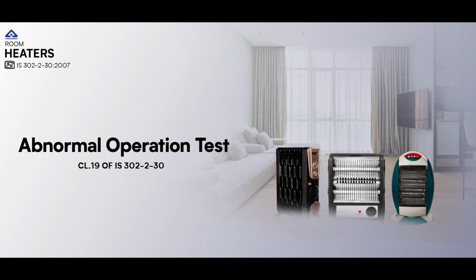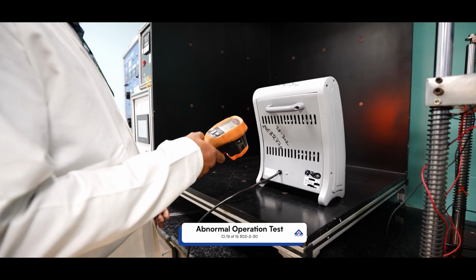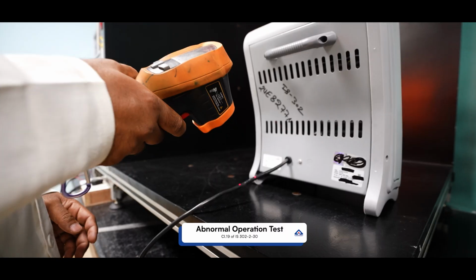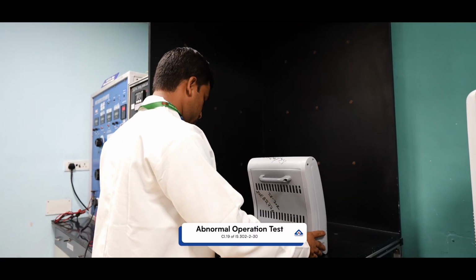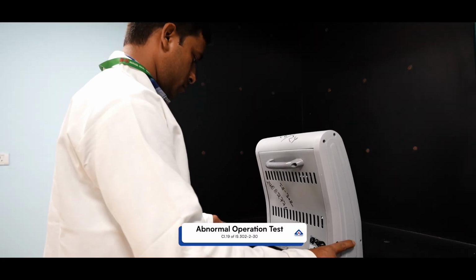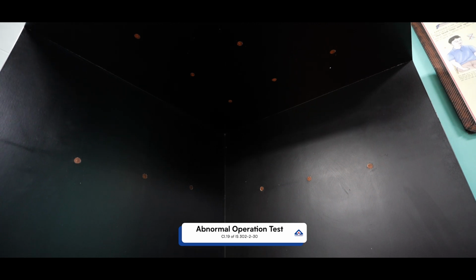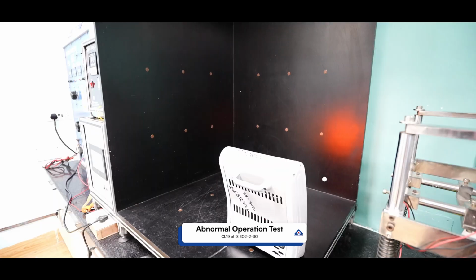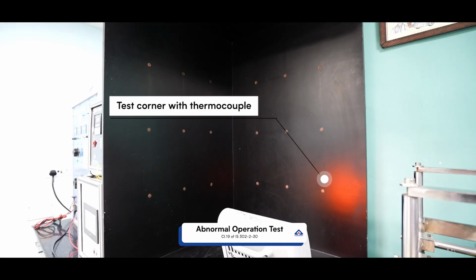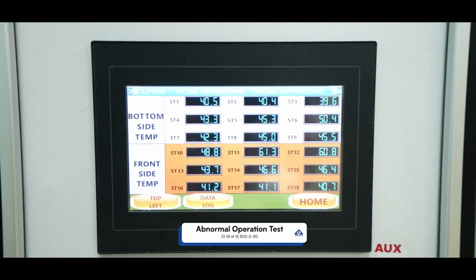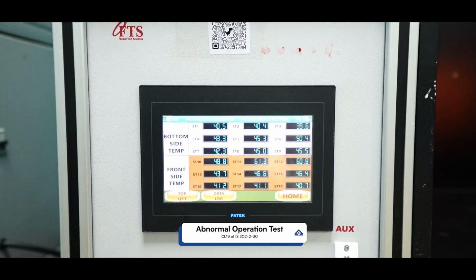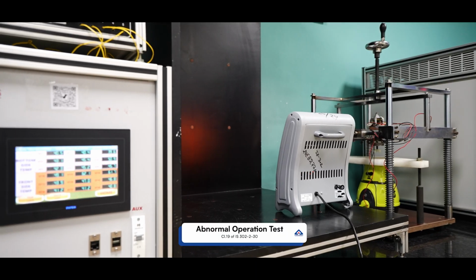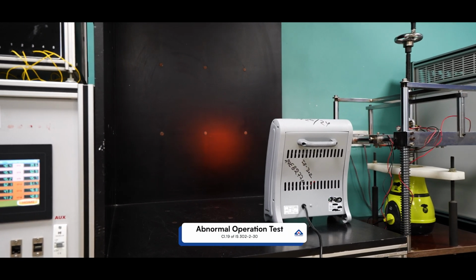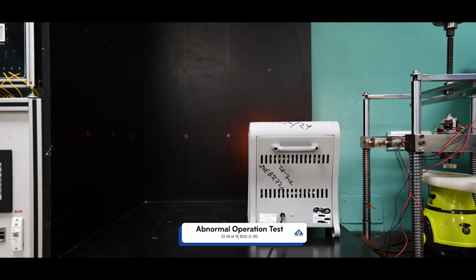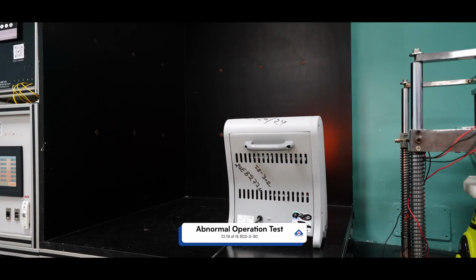Abnormal operation test. This test simulates abnormal or careless operation of the heater, such as when a motor rotor is locked or when the heater is subjected to excessive power. The goal is to check how the heater performs under such conditions and whether it could lead to fire hazards or electric shock. The heater is subjected to 1.24 times its rated power and the motor is locked for 30 seconds. We then measure the temperature rise and ensure it does not exceed safety limits. This test ensures that even under misuse or extreme conditions, the heater remains safe.